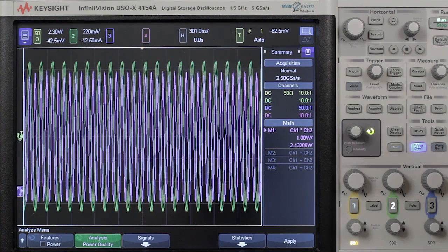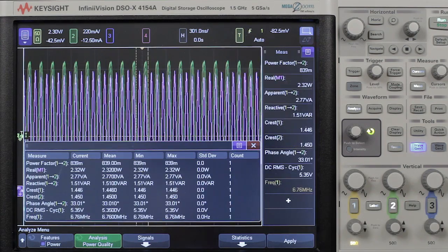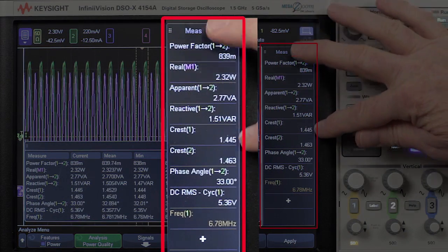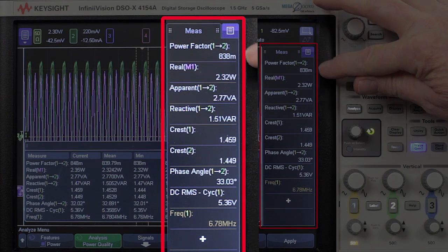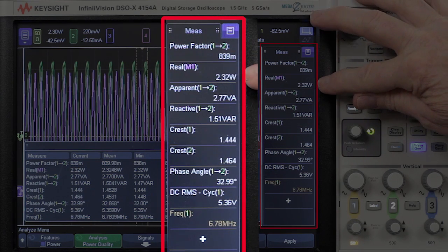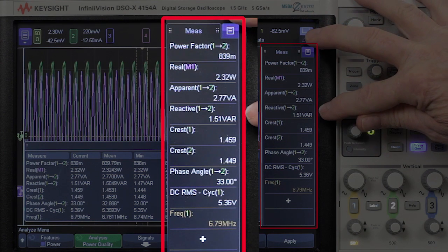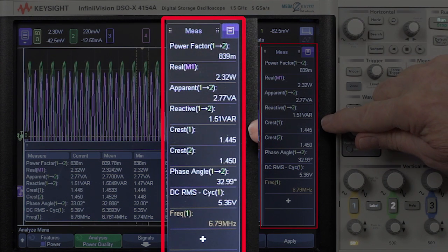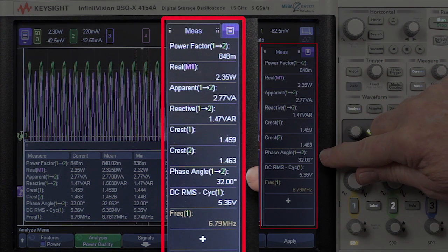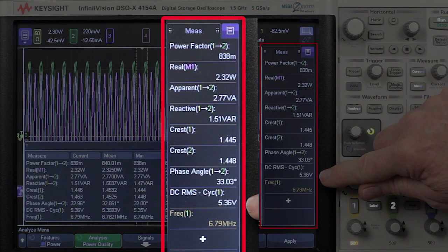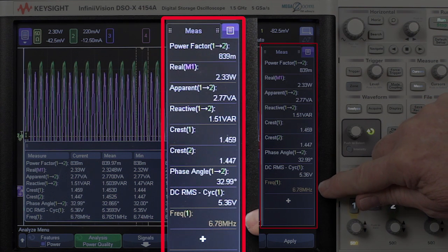This will optimize the scaling of both the voltage and current waveform and turn on the power waveform, which is the instantaneous voltage times current, and that is the purple waveform. Then I'll press apply, and here we see automatically all our power measurements. Power factor, real power, this is the one you're probably most interested in. Apparent power, reactive power, crest factor of voltage, crest factor of current, phase angle, in this case it's about 33 degrees. It turns on a DC RMS, you may not care about that one, and frequency.